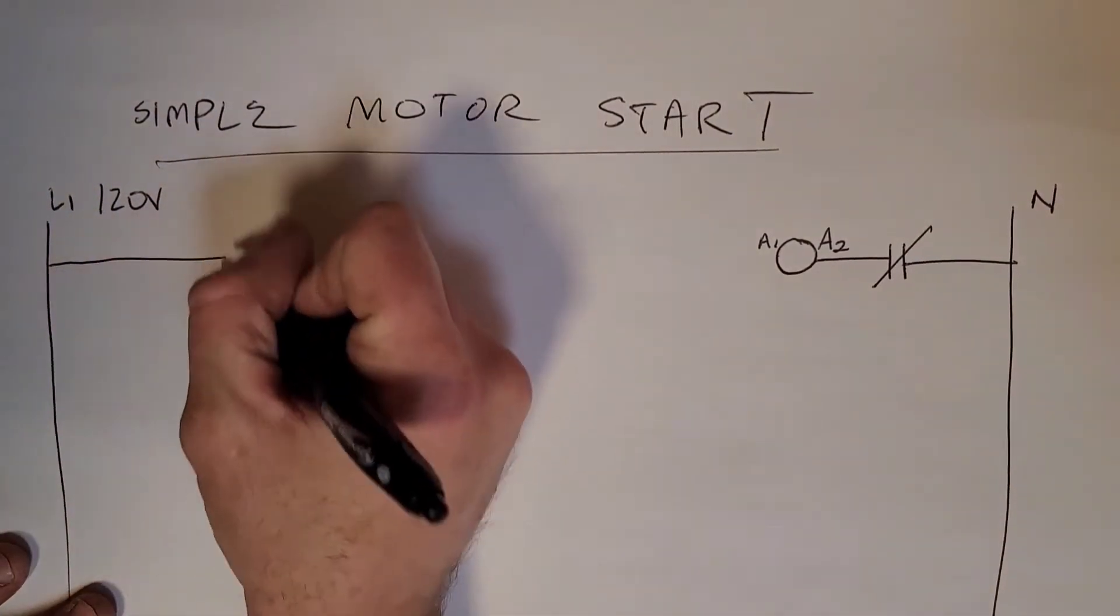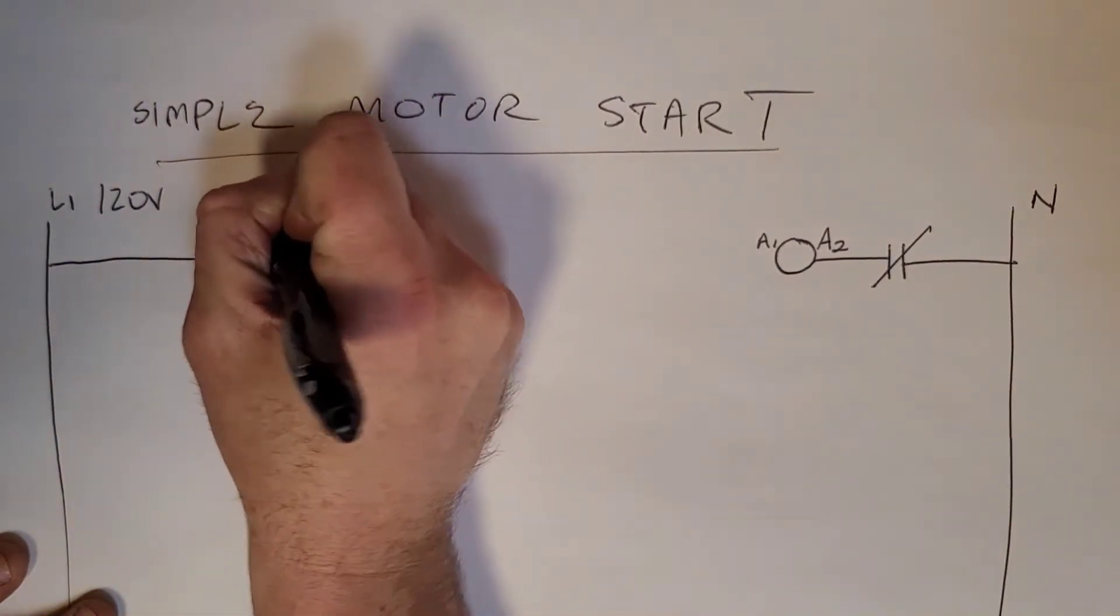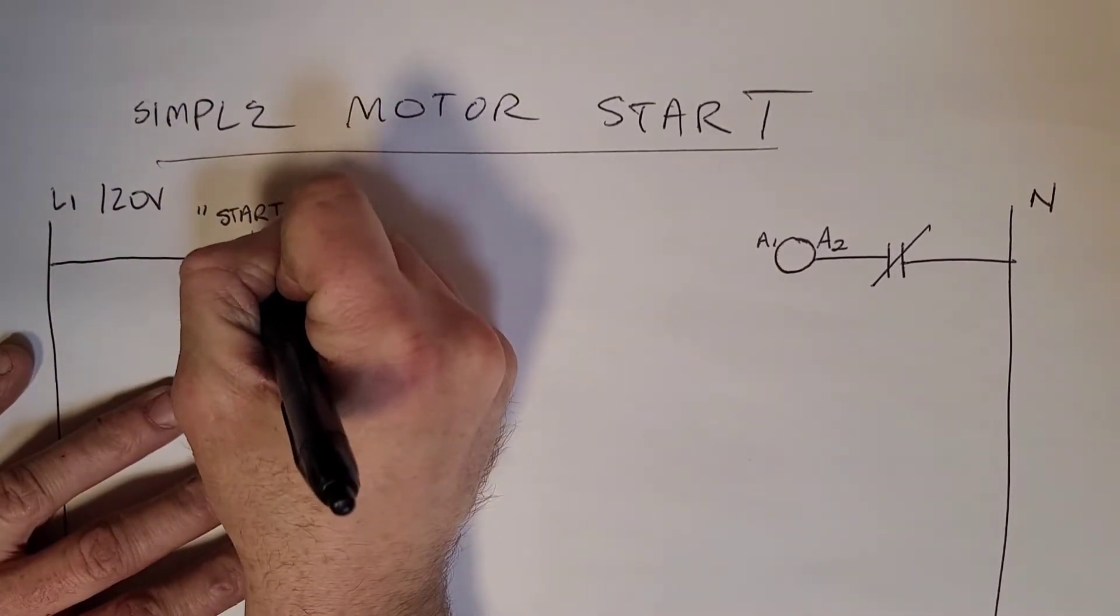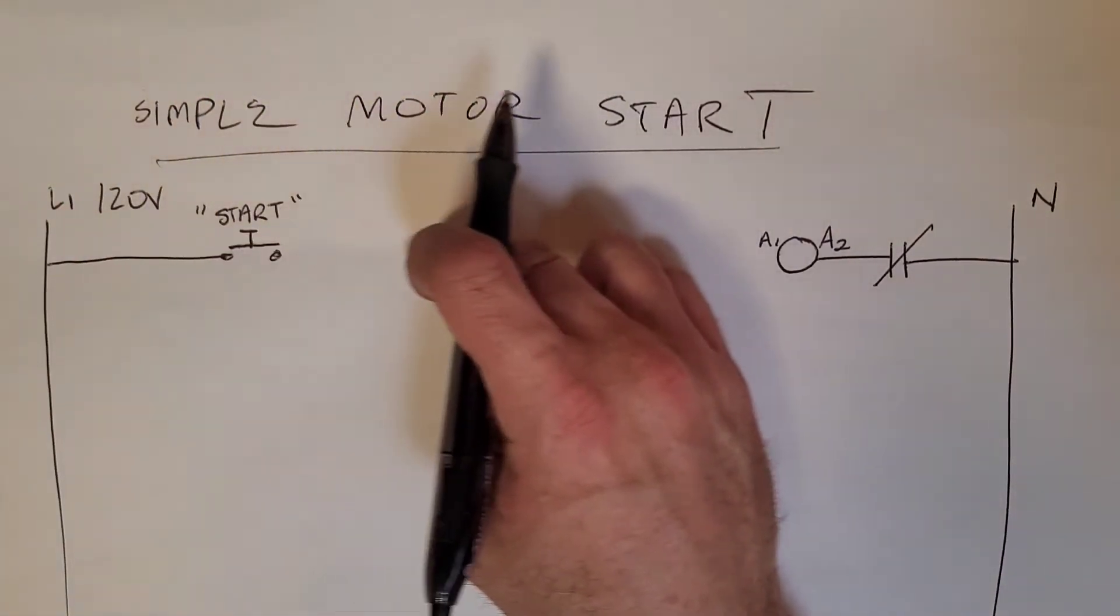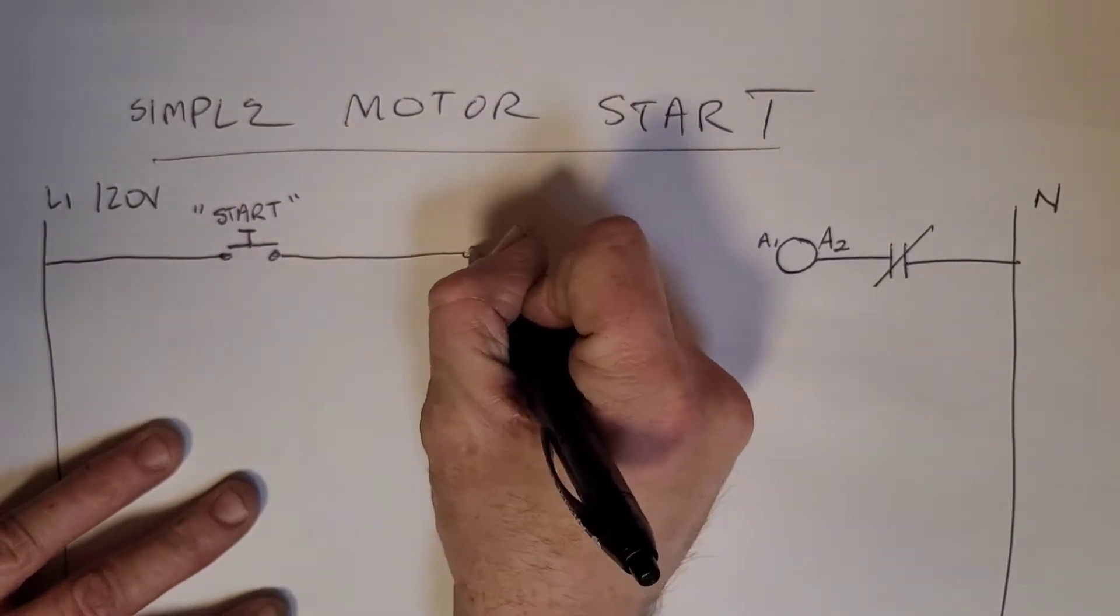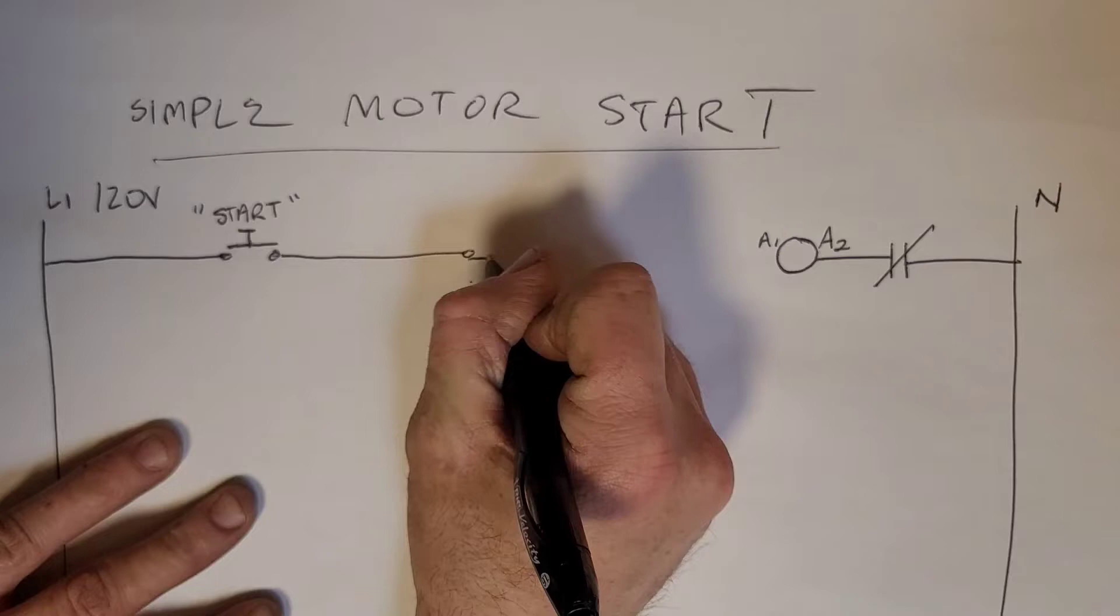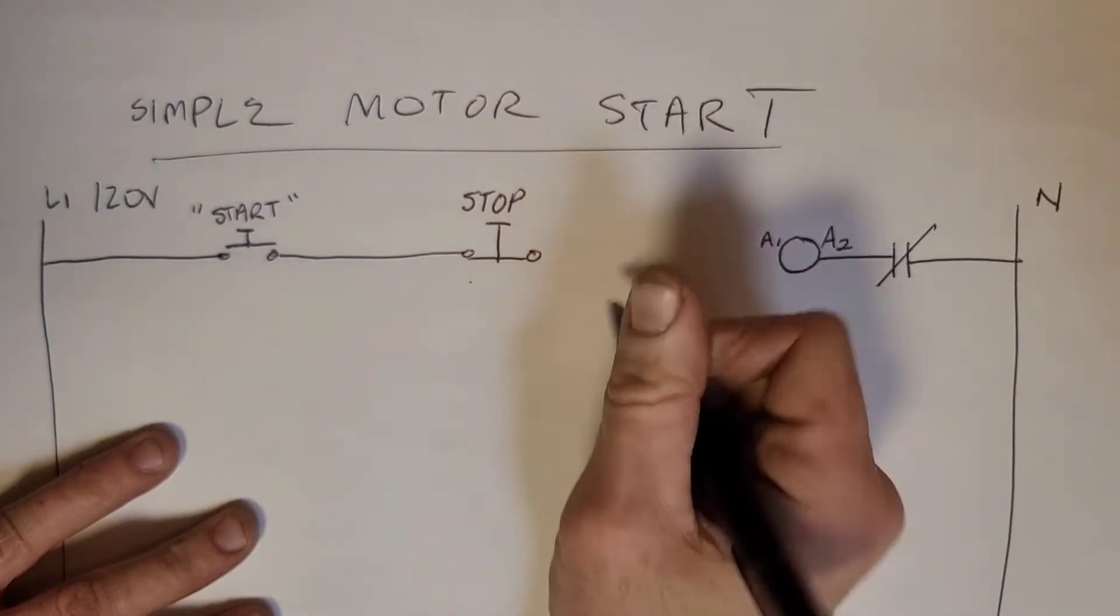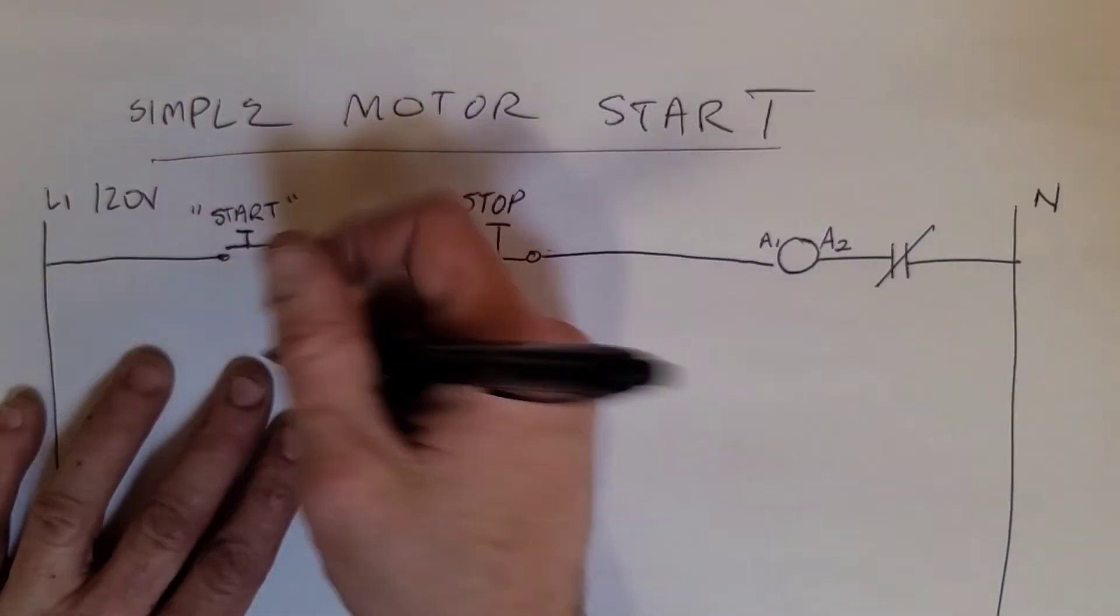What we're going to do to start our motor - this is just the control circuit - we're going to have a push button we'll call 'start'. That is going to be normally open, and then when we push it down it's going to energize that circuit and bring your 120 volts further towards your coil. We'll also have a stop button that's normally closed. When you push down on the stop button it will open up that circuit and cause it to stop.